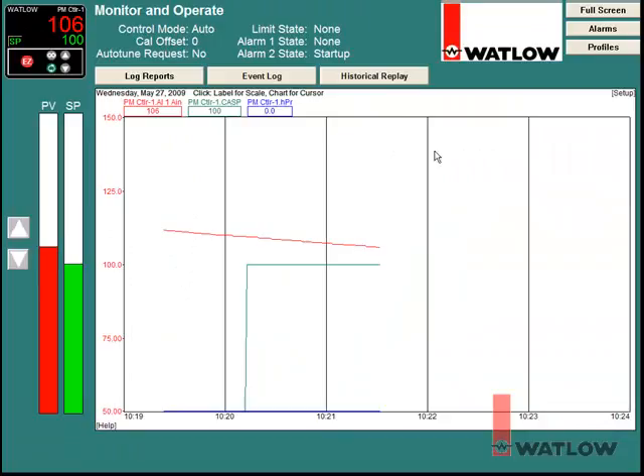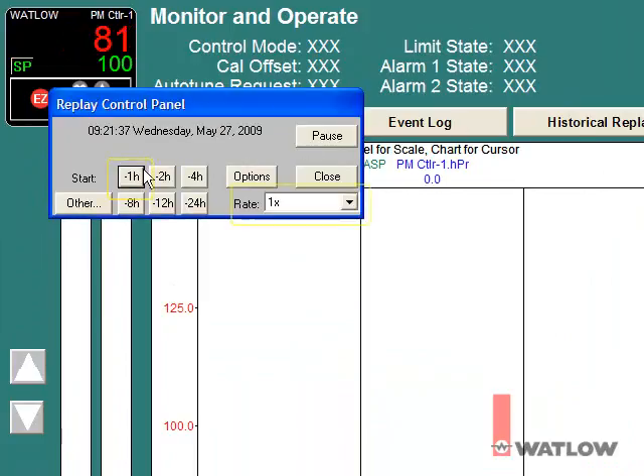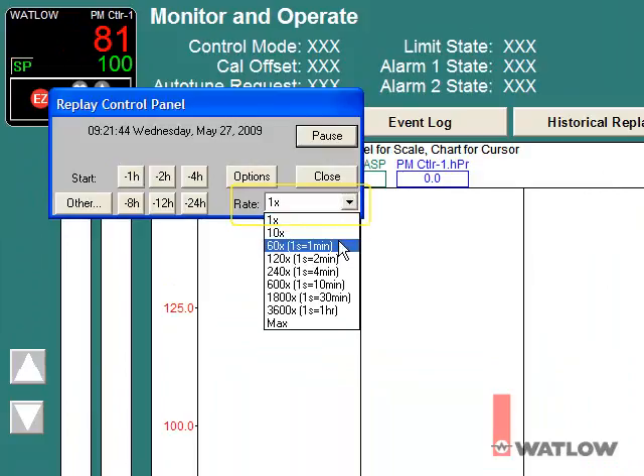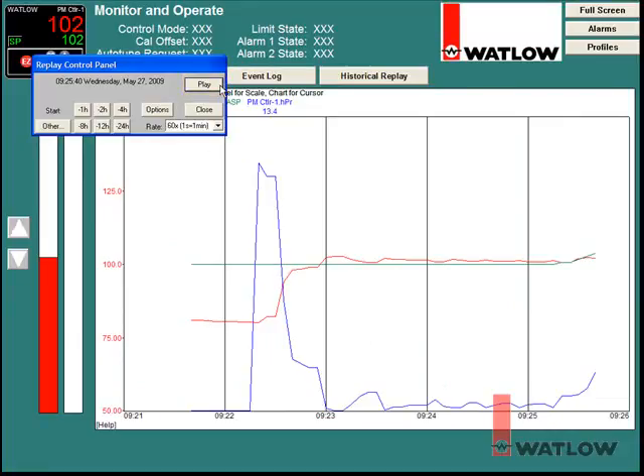The historical replay button opens a copy of the current window and the replay control panel. Click minus one H to begin viewing what was happening on this screen one hour ago. Select a rate greater than one times to speed up the replay — this can be especially helpful if something happened when no one was looking. Click Pause to pause replay. If you have purchased a historical replay option, you can go back and look at any period of time that SpecVue was running. Without that option, you can go back up to four hours. Click Play to resume.